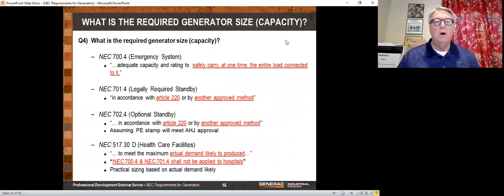Okay, generator requirements. Question 4. Here are our 4 kinds of generators, and it kind of is interesting to me that every time a National Electrical Code revision comes out, they change these definitions. If it is an emergency generator, the generator must have adequate capacity and rating to safely carry at one time the entire load connected to it. And you'll notice, what does that mean? Does that mean if you have 3 motors and one's a spare, that the generator has to provide enough power for all 3? It used to be clear.